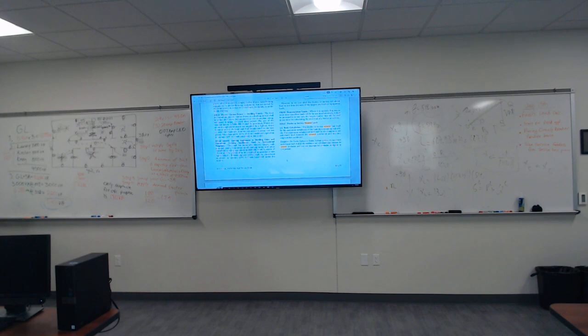So when we size our wires for our dryer and cooking, we got to size it for the hot wire and we got to size it for the neutral. Can it be both the same value? Yes, it can. But when it comes down to a lot of money being spent, right? So let's say for the dryer, dryers are typically sized 6-gauge wire. Sometimes it can be 8 to 6. Those are thick wires, right?